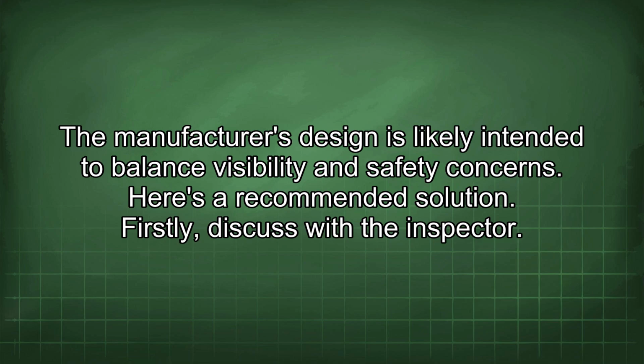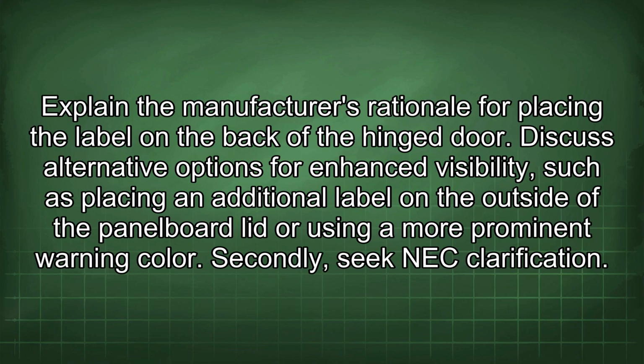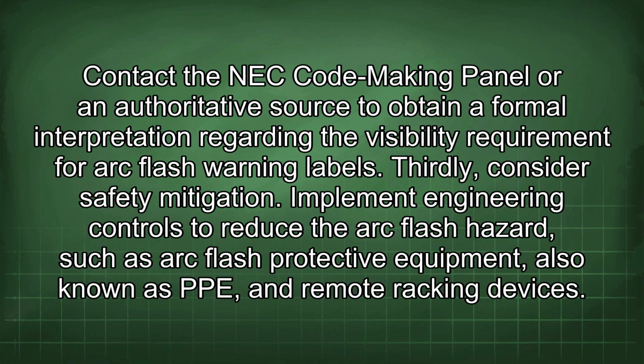Here's a recommended solution. Firstly, discuss with the inspector. Explain the manufacturer's rationale for placing the label on the back of the hinge door. Discuss alternative options for enhanced visibility, such as placing an additional label on the outside of the panel board lid or using a more prominent warning color. Secondly, seek NEC clarification. Contact the NEC code-making panel or an authoritative source to obtain a formal interpretation regarding the visibility requirement for arc flash warning labels.